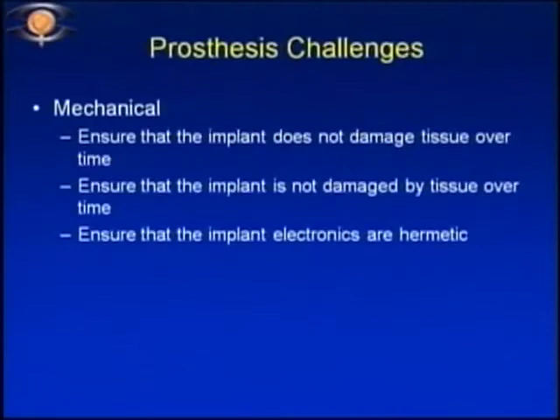And the final issue is that the implant itself, if it has any electronics, if it has any electrical components, needs to be hermetically encased. We think about these devices as having silicone or plastic on them somewhere. That plastic does not prevent water from getting in there. We think about plastic as being waterproof. Sure, it works fine for most applications. But when you put a device inside the body, inside a saline environment constantly for a decade, and enclose it in some kind of a polymer, plastic, silicone, you will actually get water vapor.